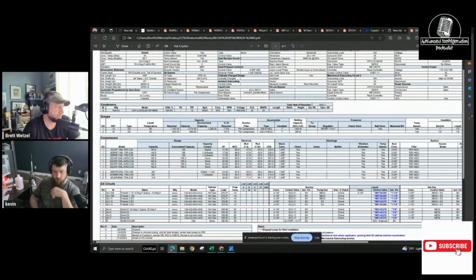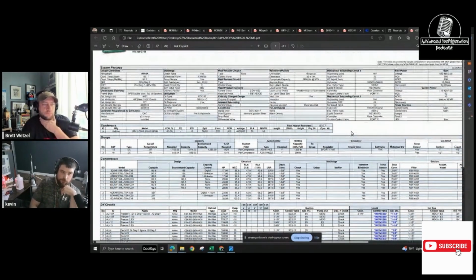Would you agree? Yeah, the only thing I would watch with the subcooler SST is the glides. Usually it's a lot higher. You could see some subcoolers at 87 pounds of R448, and that's around a 50 degree SST. So that's your glide. Some of these heat exchangers are hitting 2-3 degree TDs, so they're super efficient. So that's one thing to keep in mind. Some of these are raised up a little bit, and with some of the sheets, just take it with a grain of salt.